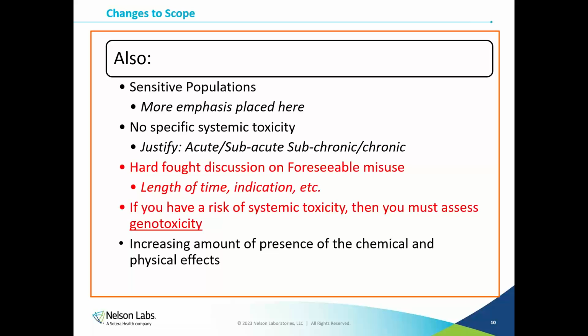Yeah, and in addition, Thor, I would add, I think a lot of people on this call maybe don't have a lot of experience with understanding misuse and device failure because in a lot of cases, company dependent, manufacturer dependent, these responsibilities may fall within the engineering departments, right? More upstream. And what used to be considered within design verification and validation, as in misuse and failures, right? Identifying those potential failures now also has a little bit of overlap with our biocompatibility teams here at the manufacturer as well.